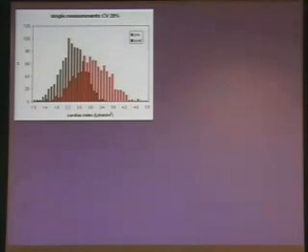If you imagine a situation where the cardiac output drops by 25%, so you start with a cardiac output of 3 and go down to 2.25, I think most of us would agree that a 25% drop is significant. Then you simulate those measurements on a highly variable tool, which has a mean bias of 0. So it's spot accurate in terms of the average cardiac output, but the coefficient of variation is 20%. The coefficient of variation is the standard deviation divided by the mean, expressed as a percentage.